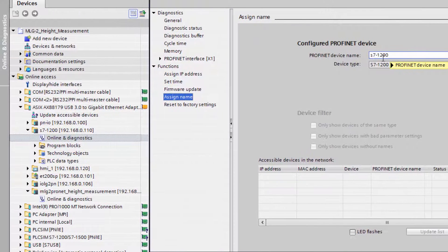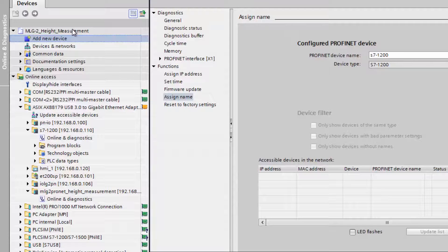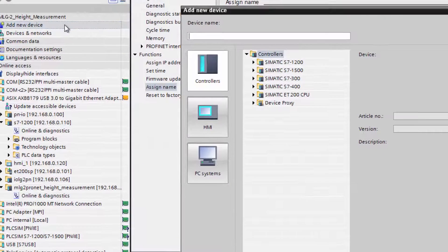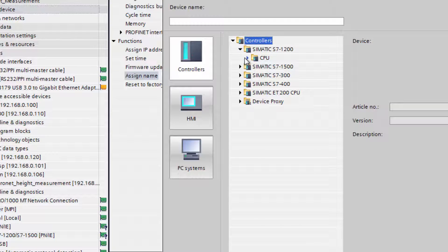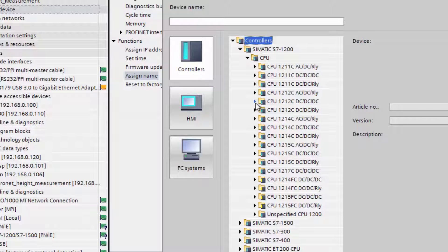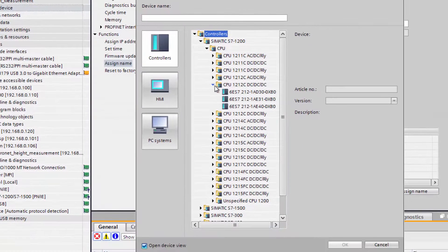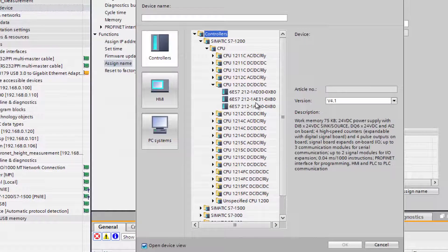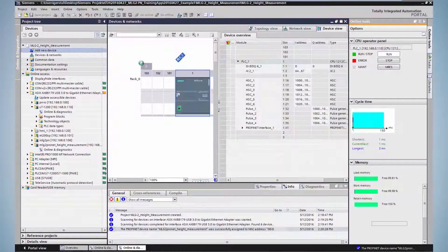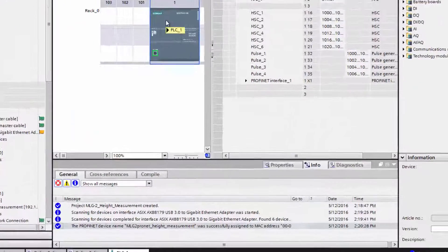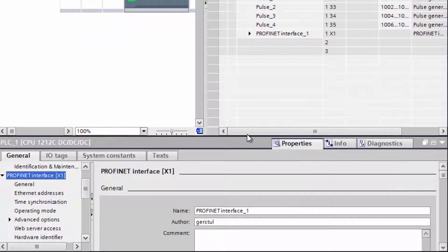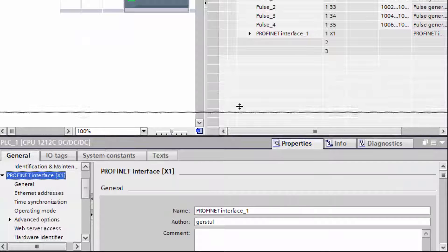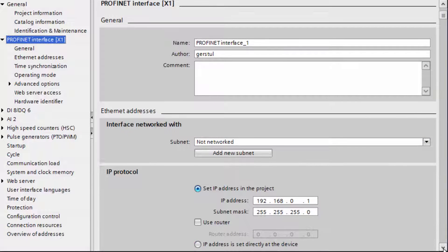First the PLC has to be added to the project. Click on Add New Device. Select your PLC from the tree structure. In this example it is an S7-1200 with a CPU 1212C DC-DC-DC. The correct version is selected. Now select the PLC's properties and tick the corresponding boxes to keep the PLC's IP address and the device's PROFINET name.